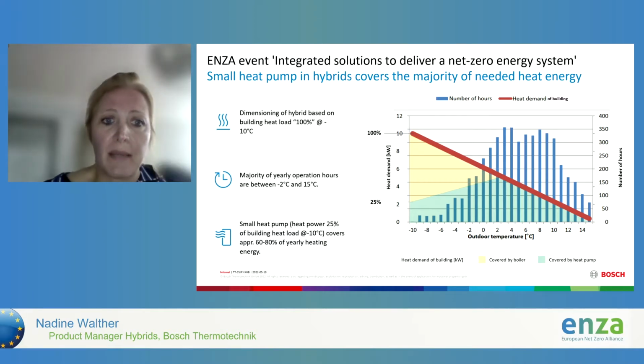So the dimensioning of the hybrid is usually based on the building heat load with 100% at minus 10 degrees. And the majority of yearly operation hours of the heat pump, as just said, are between minus 2 degrees and 15 degrees. And every building has, depending on its insulation status, a heat demand. So the blue bars represent the hours, as said, that the heat pump is being used. And the contribution, how this energy is provided, is represented by the yellow for the boiler, and green represents the coverage of the heat pump.